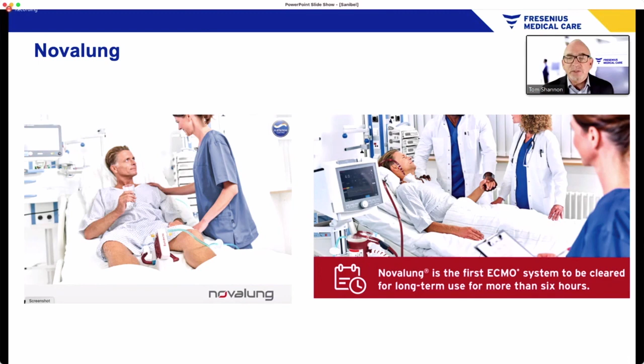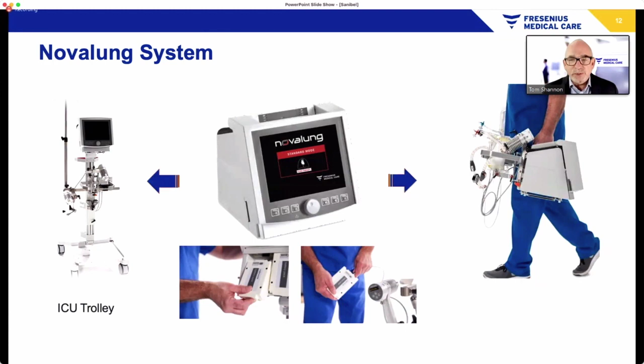So I figured I would go through the system really quickly since I only have a few minutes, but I wanted to, if you haven't seen it before, since there haven't been a lot of trade shows this past year, you may not have gotten an opportunity to see it in person. The console can be displayed on a cart, which you can call our trolley, but it can also be in a transportable mode, as you can see on the screen here, being carried with the disposable mounted to the back of the device. What's unique about the system also is that it has hot swappable batteries. The two batteries within the system make it very easy to stay on support for quite a long time. Additionally, those batteries can be connected directly to some of our motor drives for backup, as well as potential transport options.